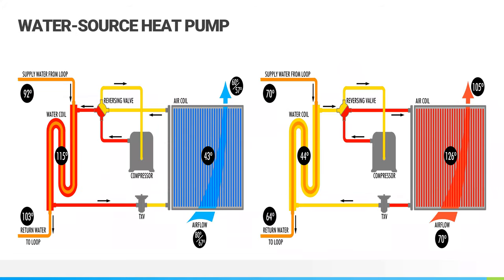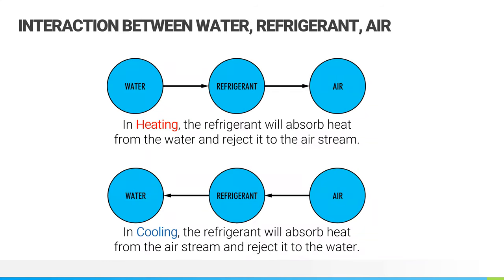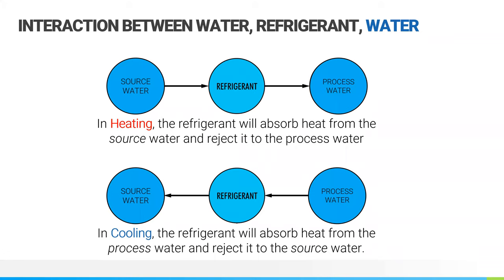You've also got what are known as water source heat pumps. The big difference here is that instead of an outdoor condenser, you've got a water loop carrying that energy to or from the heat pump unit. On the simplest side of things, in heating mode you've got a water loop transferring energy through the refrigerant to air, and in cooling mode you've got the opposite, where the refrigerant's absorbing heat from the airstream and rejecting it to the water. There are also water-to-water heat pumps, which are really no different than your water-to-air, except you're transferring heat energy to and from what I call a process water loop, which is for radiant floors, radiant cooling, snow melt, those types of applications that you'd see in the HVAC world.